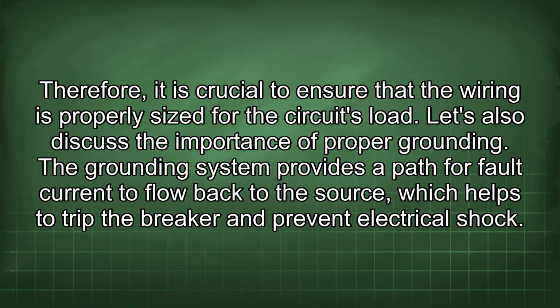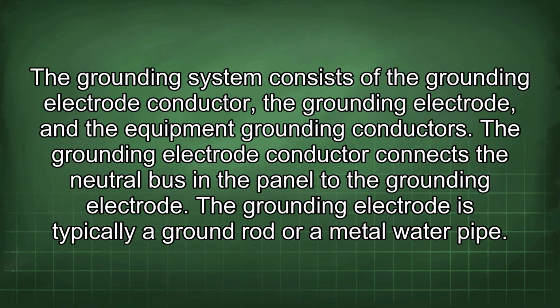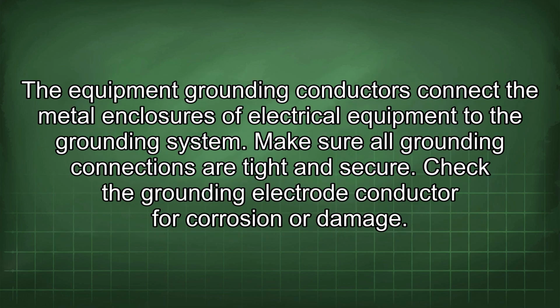Let's also discuss the importance of proper grounding. The grounding system provides a path for fault current to flow back to the source, which helps to trip the breaker and prevent electrical shock. The grounding system consists of the grounding electrode conductor, the grounding electrode, and the equipment grounding conductors. The grounding electrode conductor connects the neutral bus in the panel to the grounding electrode. The grounding electrode is typically a ground rod or a metal water pipe. The equipment grounding conductors connect the metal enclosures of electrical equipment to the grounding system.